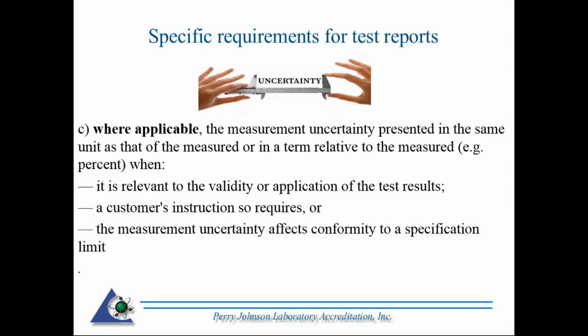Uncertainty, and I highlighted where applicable, which is different than calibration. Where applicable for test reports, the measurement uncertainty is presented in the same units as that of the measurand, and in terms relative to the measurand, such as percent. When is it applicable? When it is relevant to the validity or application of the test results, a customer instruction so requires, or the measurement uncertainty affects conformity to a specification limit. You say pass, fail. Measurement uncertainty may actually need to be taken into account in those situations.